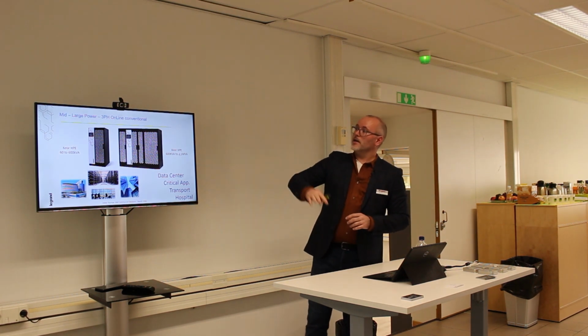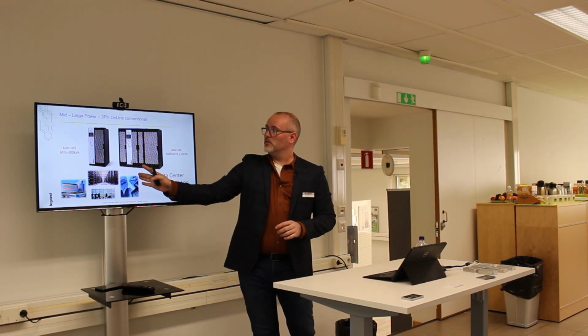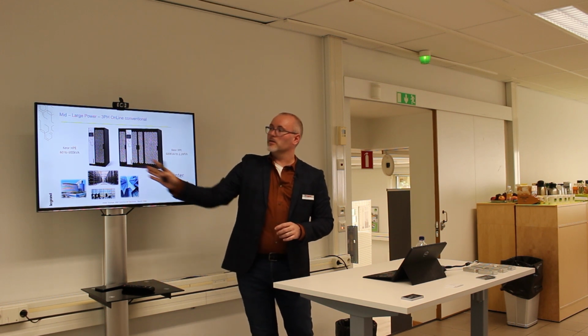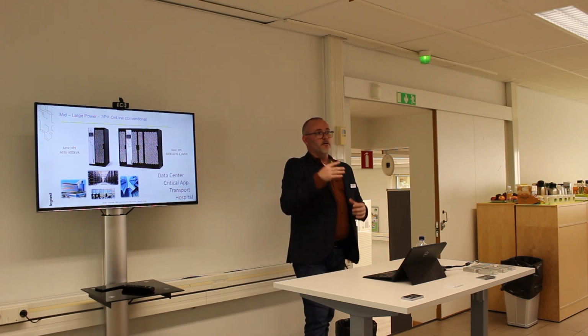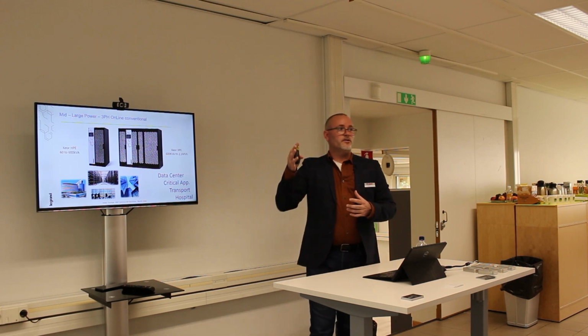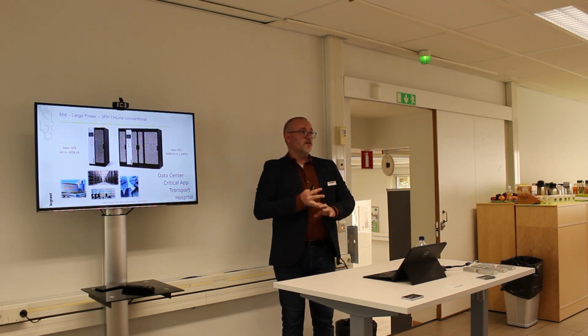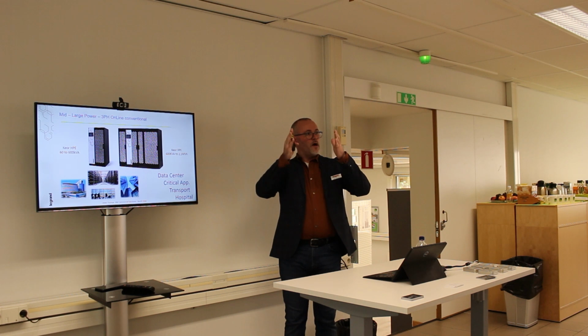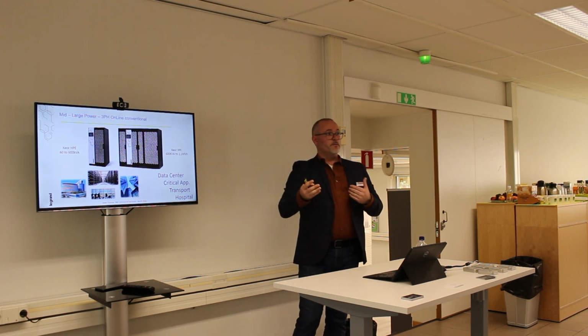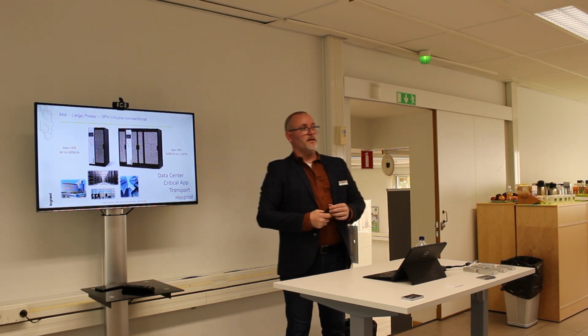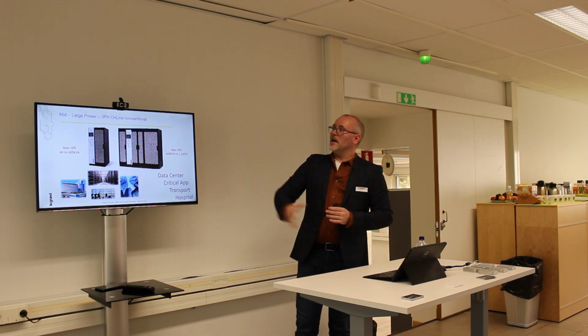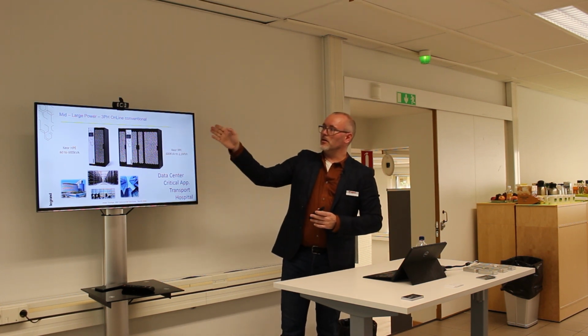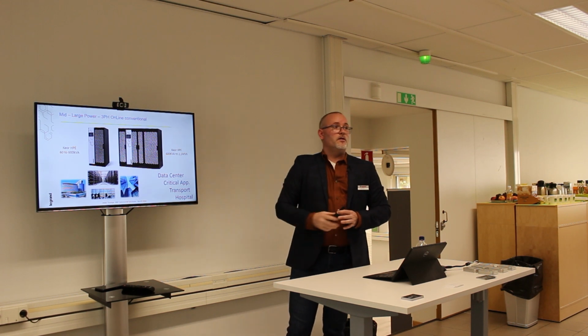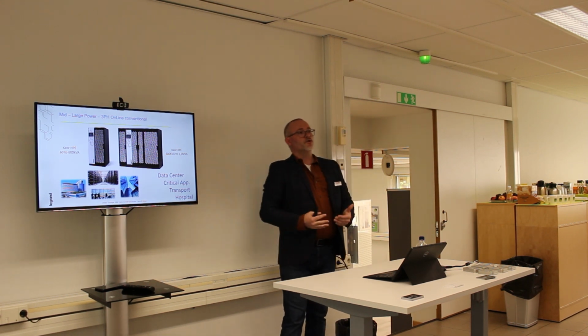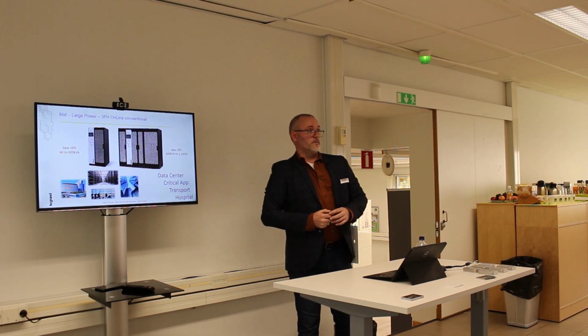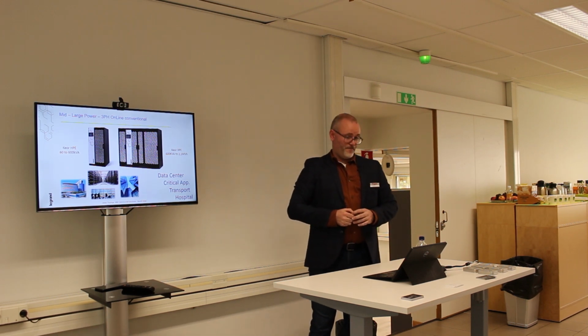In these cases here, you have a bypass module - the small cabinet on the side will be a bypass unit. Here you have all the electronics, all the breakers that you need. You have one cabinet where you enter to do your main maintenance and control of the unit, and then you simply add units on the side with batteries, depending on how you want the load to be balanced or controlled.